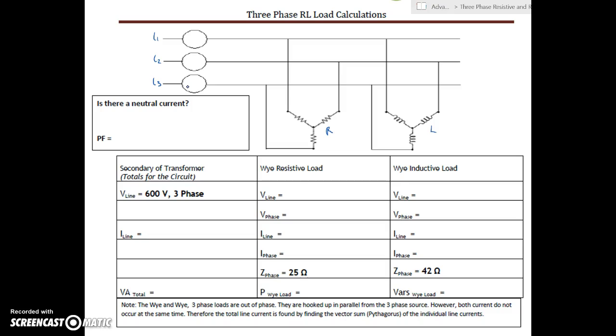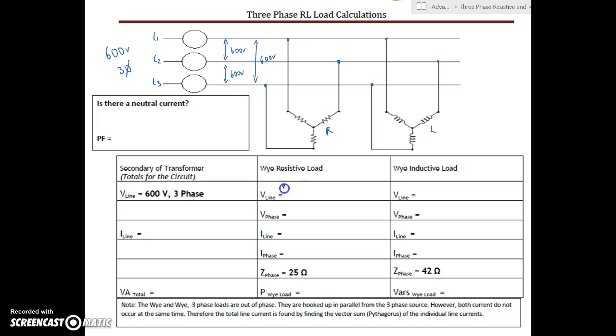This resistive load could be a three-phase resistive heater, and the inductive load could be a three-phase motor, Y-connected — maybe a heater and blower fan that are part of the same unit. We need to know the total current that unit will draw. First, we look at the incoming voltage: 600 volts three-phase, meaning 600 volts line-to-line. Those voltages appear across both the resistive and inductive Y loads, since they're in parallel.